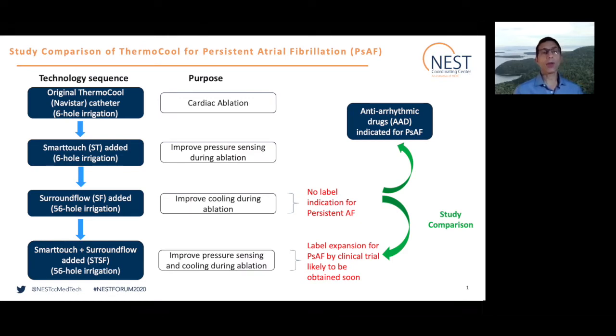So the evolution of the technology: the original ThermoCool or Navistar catheter was intended for cardiac ablation, and it had 6 holes for irrigation to cool the tissue around the catheter. Then a smart touch function was added, and this allowed feedback on how much pressure was being applied by the electrophysiologist with the catheter in the atrium, so that the depth of the ablation could be monitored. The next technology was the surround flow, which improves the cooling during ablation by adding 56 holes rather than 6 holes. And then the two of these were combined into the STSF, which has both the improved pressure sensing and the cooling during ablation, and has 56 holes for irrigation.